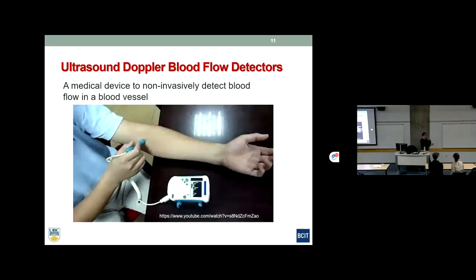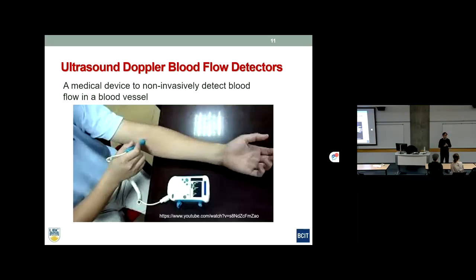If a physician traces the carotid artery and reaches a bifurcation, they can detect whether there's blood flow in each branch or not. If blood flow velocity is fast, it generates a higher-pitch or higher-frequency sound. So by listening to the pitch, you can tell how fast the blood is flowing. If most of a blood vessel is clogged, the remaining open section is very small, so the velocity will be fast. Tracing along the artery and hearing a very high pitch indicates that section is restricted — that's the basis of diagnosis using this device.